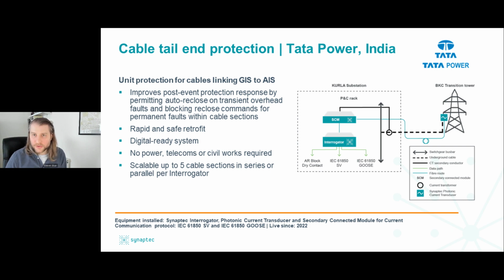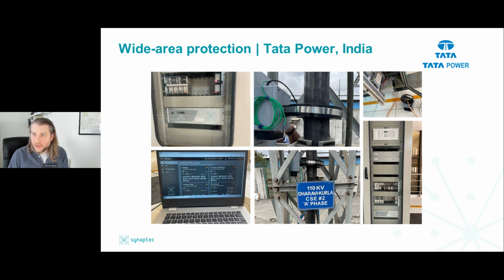So the system will provide a clear signal to either block or allow auto reclose for all foreseeable fault types and positions. So in this particular deployment, even though these cables are relatively short sections going from the substation to the transition point, this will carry some risk around cable faults not being dealt with correctly, but this solution eliminates that scenario entirely. Also, in general, this solution scales up well for more complex scenarios where there are multiple conductors, perhaps parallel conductors, and also if there are multiple transitions over a significant distance. And finally here, there are just a few pictures of that installation where you can see some of the CTs, which are coupled to a fiber, and then all of the measurements are brought back to a central location in the substation.